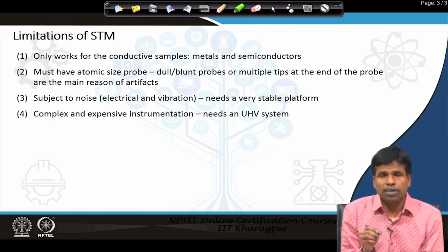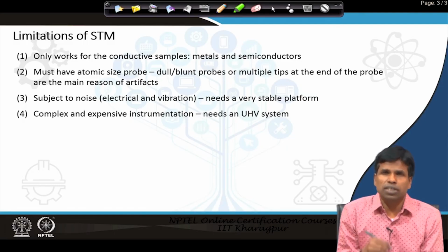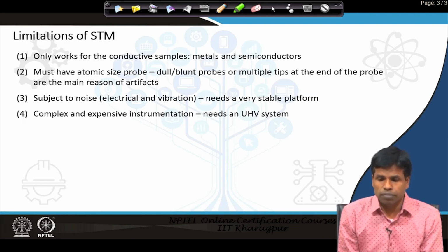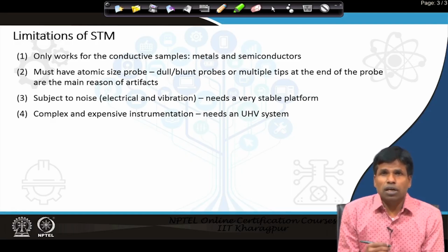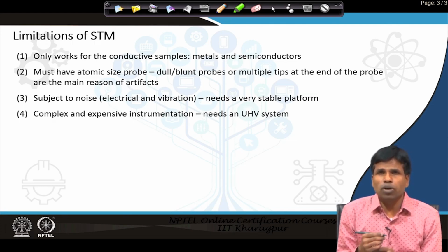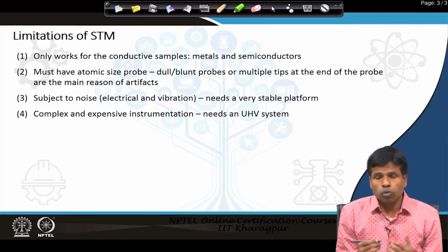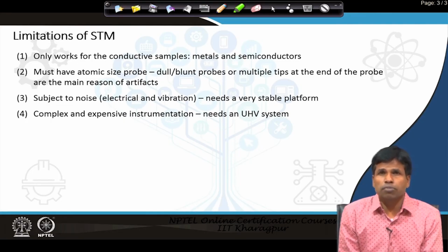If our tip is dull or blunt or has a larger size, then our lateral resolution will also degrade, or the image can have artifacts. So, a dull probe or multiple tips would become a problem for the scanning tunneling microscope. Moreover, as we measure the tunneling current, and the tunneling current can only be measured when the tip and sample are brought very close to each other at a distance of a few angstrom, we should have complete vibration isolation. Any type of small vibration cannot be accepted to get information at the atomic level. So, one of the issues is that it is subject to noise.